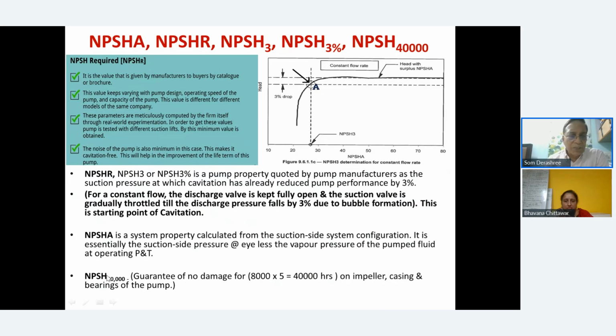Then NPSH-A we have already discussed. Then NPSH 40,000 also is sometimes a nomenclature which is used. This is actually a guarantee for no damage, because if the cavitation does not happen, there is no damage to the impeller or the pump casing. So the manufacturer gives you NPSH 40,000. What is that? That is 8,000 hours into 5 years guarantee it is giving you. That is a standing guarantee that this pump, if it is operated above this required NPSH R, will stand NPSH 40,000.